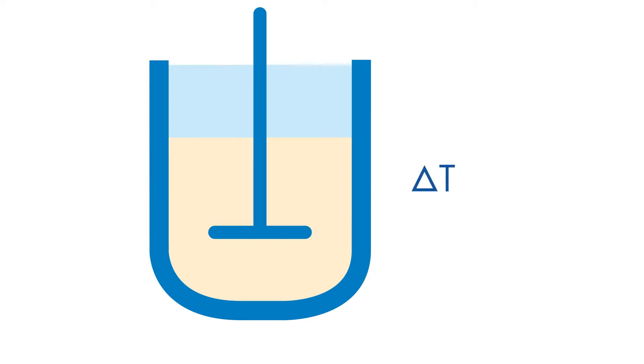The heat flow principle follows the concept of measuring the driving force, delta T, which is the temperature difference between the temperature of the reaction mass, TR, and the surrounding temperature, TJ, as delta T is a measure for the power of the reaction.